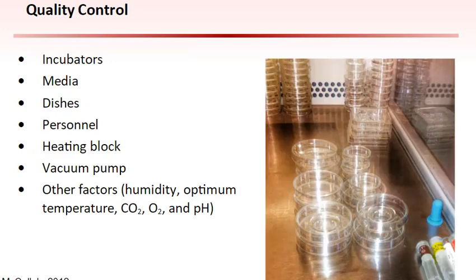All of the environmental conditions and equipment functions should be documented as within tolerable levels at least daily. Any equipment for which intolerable values are found should be corrected and should not be used until proper function can be documented. Small fluctuations of incubator conditions have been associated with increased incidence of spontaneous pregnancy losses weeks after the incubator exposure. Therefore, it is imperative to maintain conditions within predetermined tolerable limits for all rooms and equipment at all times.